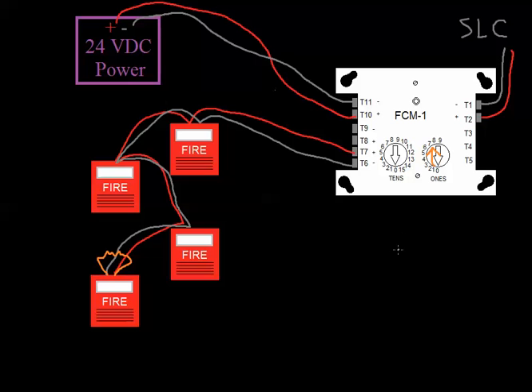So as we know, everything in a fire alarm system has to be supervised. And we know that the module is going to be supervised because we're going to go into the program and tell it to pull or look for address 8. We're going to tell it's a control module, so the panel is going to be constantly checking for module 8. So the data circuit is supervised in that way. If there were an open on this circuit, on the output circuit, it's going to show up as a trouble. Internally, this thing knows to supervise, to basically monitor the current on terminals 6 and 7 in the standby state. So if something happened to this wiring, it would go into trouble. It would say open circuit, module 8.